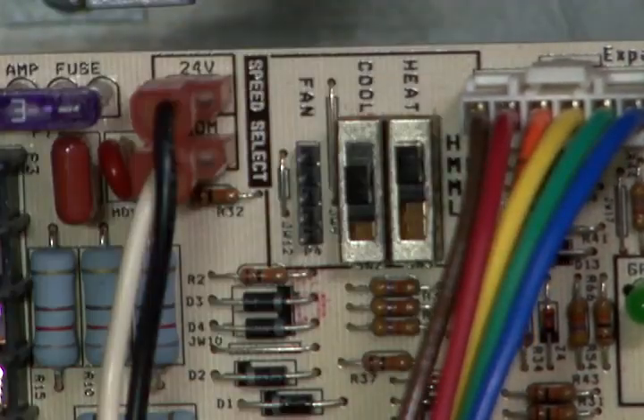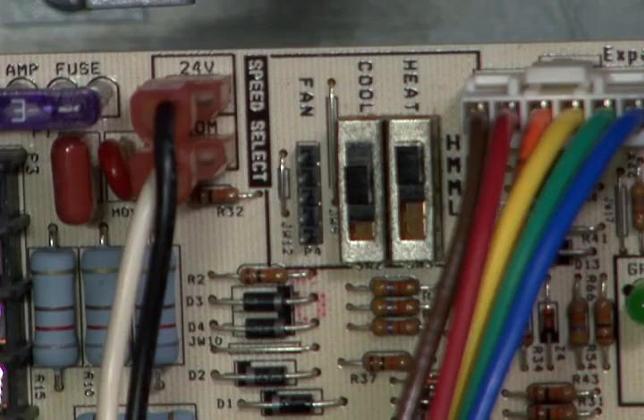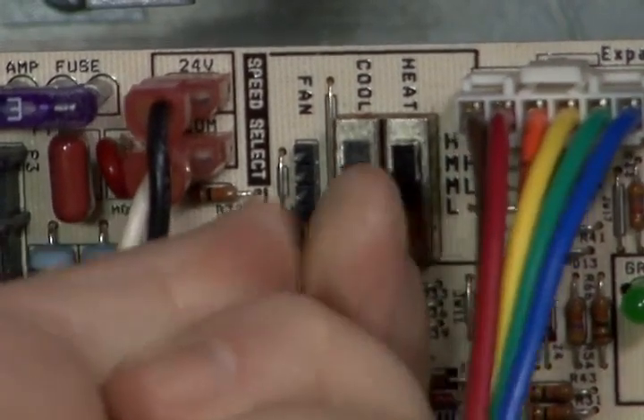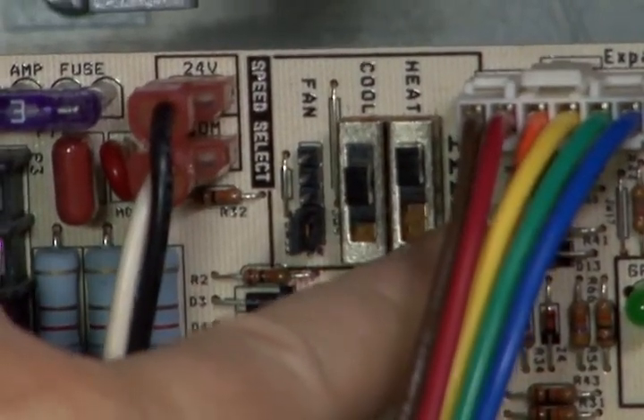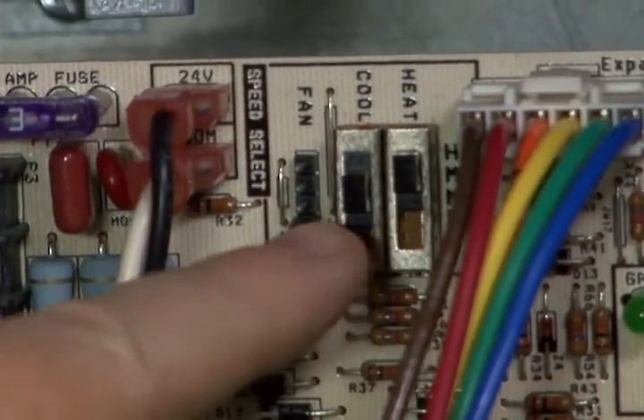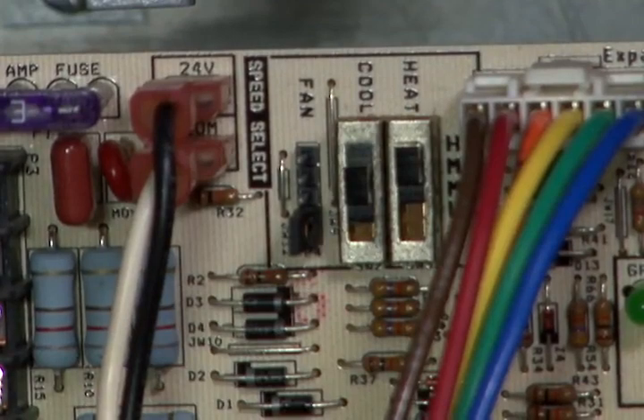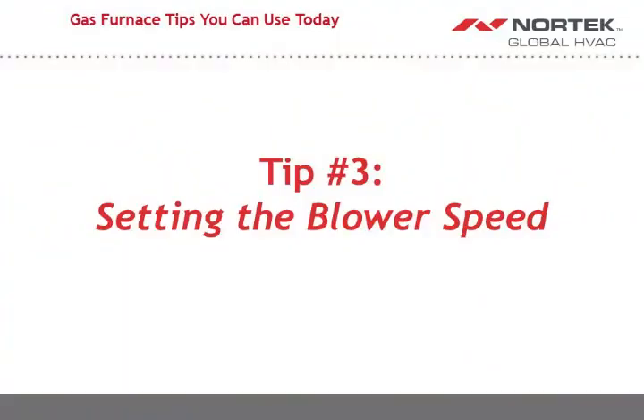The black plastic jumper shunt that's labeled fan is for continuous fan operation. All you're going to do is line that black plastic shunt up with the designated speed on the board that you want. So when you are just running a continuous fan to circulate air in the home, you can designate that by speed. You could have all three of them be the same speed, or you could have each one of them be a completely different speed. But that's just how easy it is to change or to alter or to set up the blower speeds on the single stage gas furnaces.